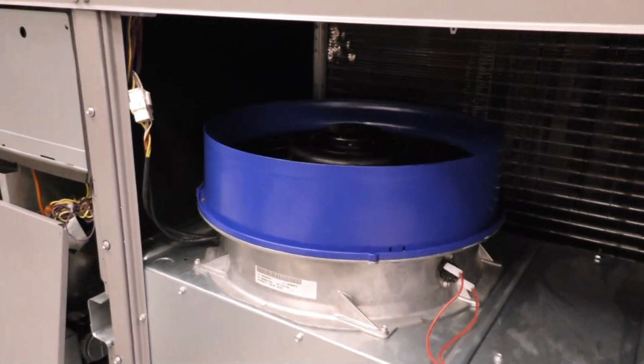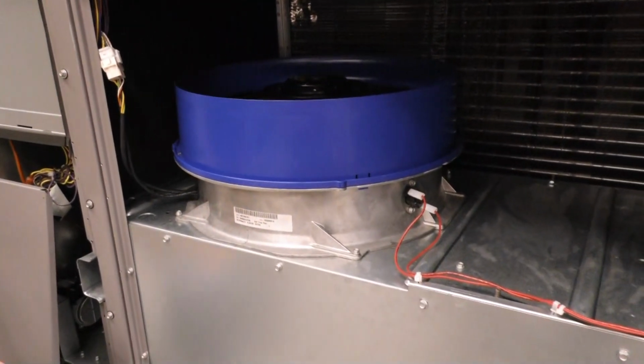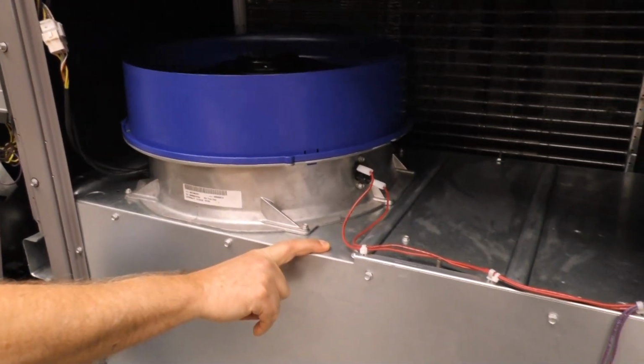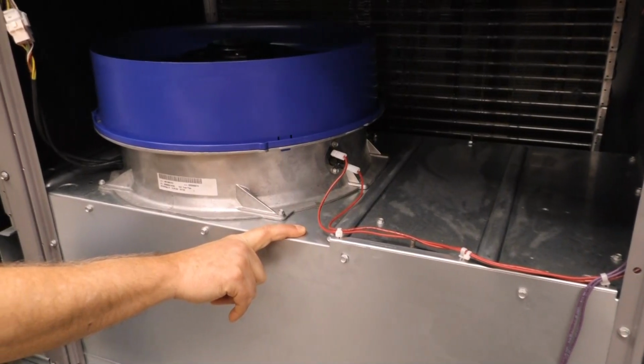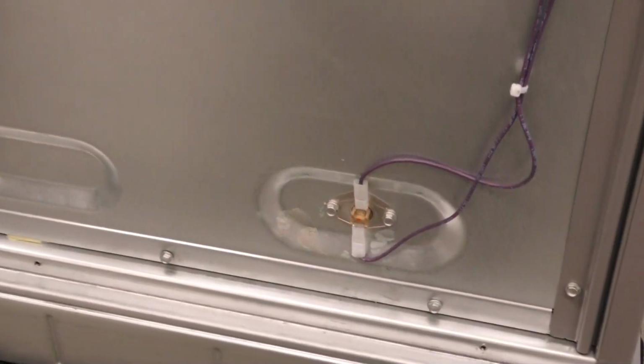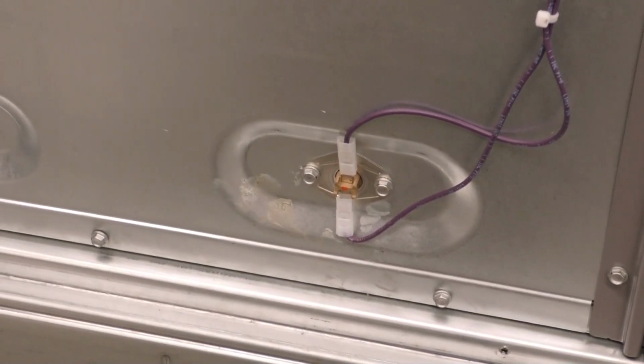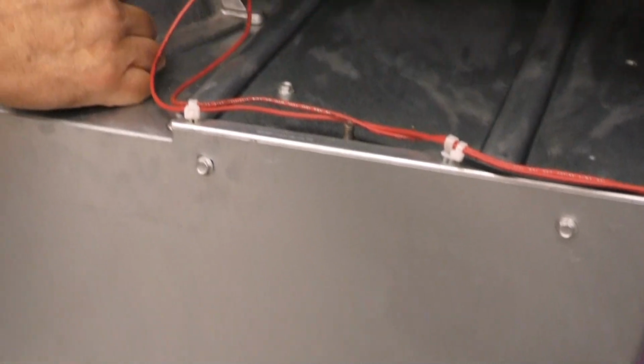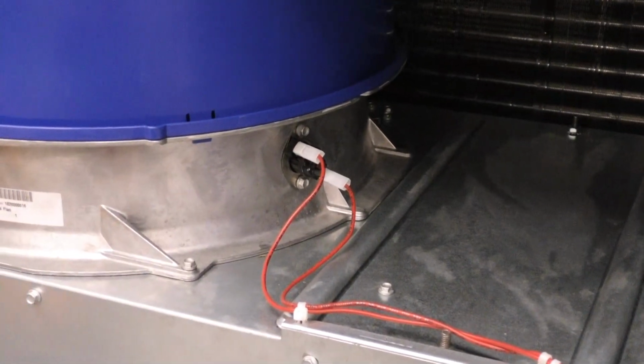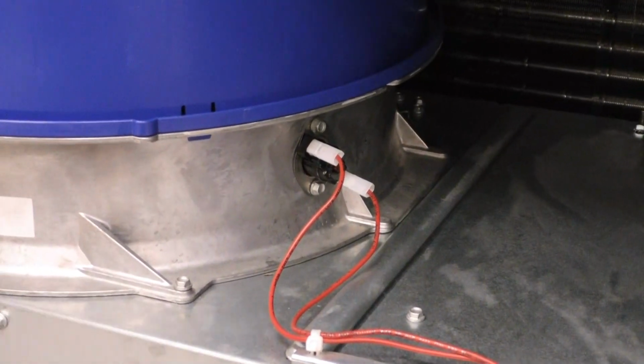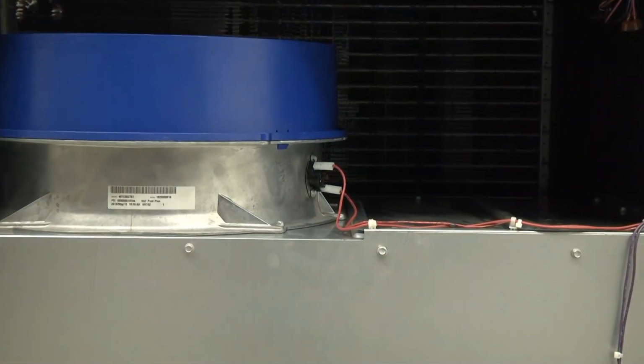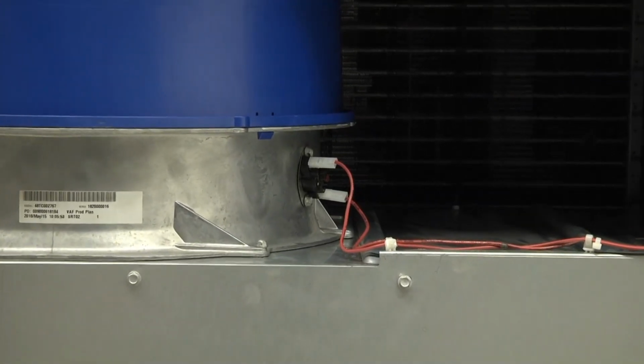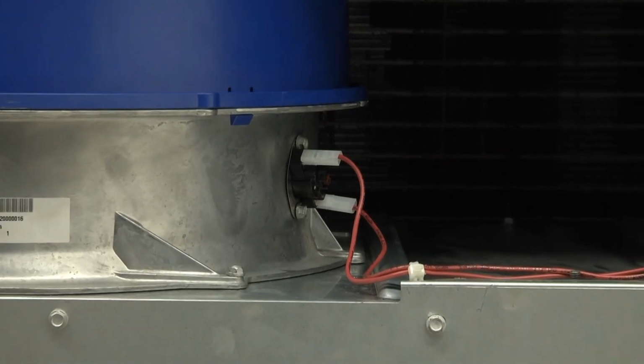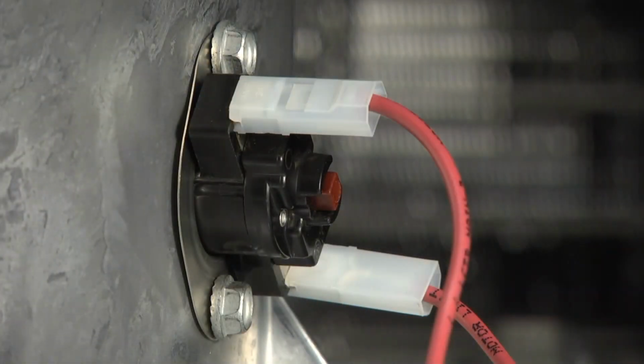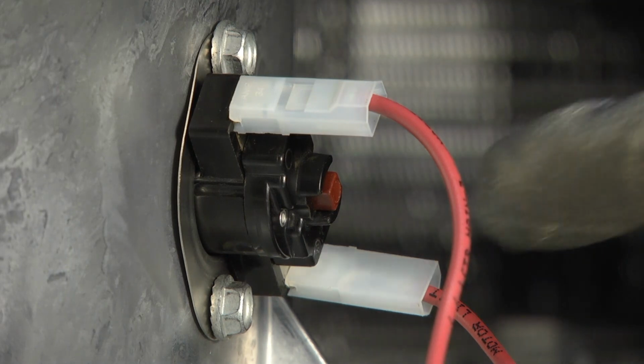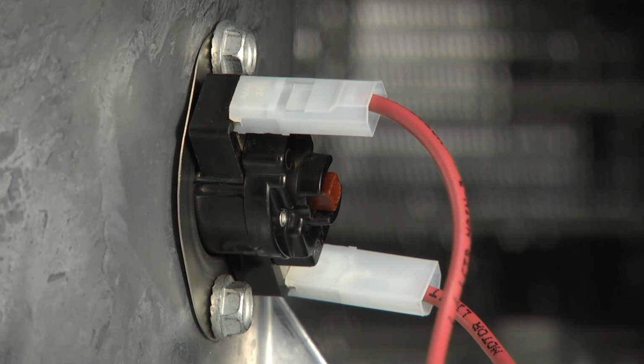This being a gas heat machine also requires that we relocate the limit switch, which was normally installed directly above the heat exchangers in the fan compartment, to a lower level on the heat exchanger access panel. There's one additional temperature sensor that's installed on the housing for this particular fan assembly, and that is an additional safety due to the composite nature of the scroll and the fan wheel itself. One other thing to point out is that the stator temperature limit switch located on the indoor fan casing is a manual reset limit switch. So, if the temperature gets too high and it trips, you'll need to physically press the red reset button to reset it once things have cooled down and any issues have been addressed.